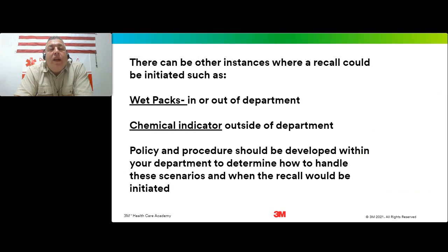So when could there be other instances? We release the goods and potentially an end user opens up a package and there's a wet pack. Maybe there's moisture inside the devices we sterilized. What if the chemical indicator didn't turn? We're not going to know that down in SPD - the end user is going to know that when they open up the package. So that's going to trigger an alarm again.